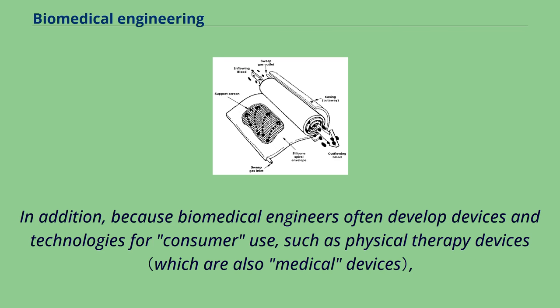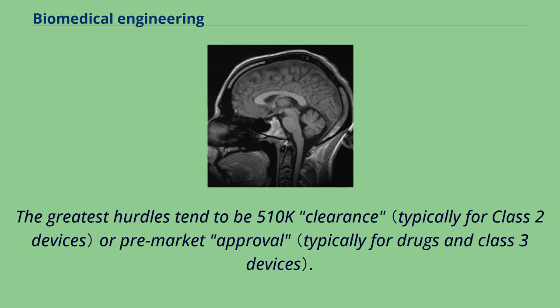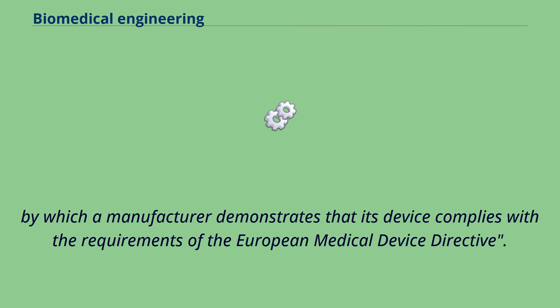Because biomedical engineers often develop devices and technologies for consumer use, such as physical therapy devices, these may also be governed by the Consumer Product Safety Commission. The greatest hurdles tend to be 510k clearance or pre-market approval. In the European context, safety, effectiveness and quality is ensured through the conformity assessment, defined as the method by which a manufacturer demonstrates that its device complies with the requirements of the European Medical Device Directive.